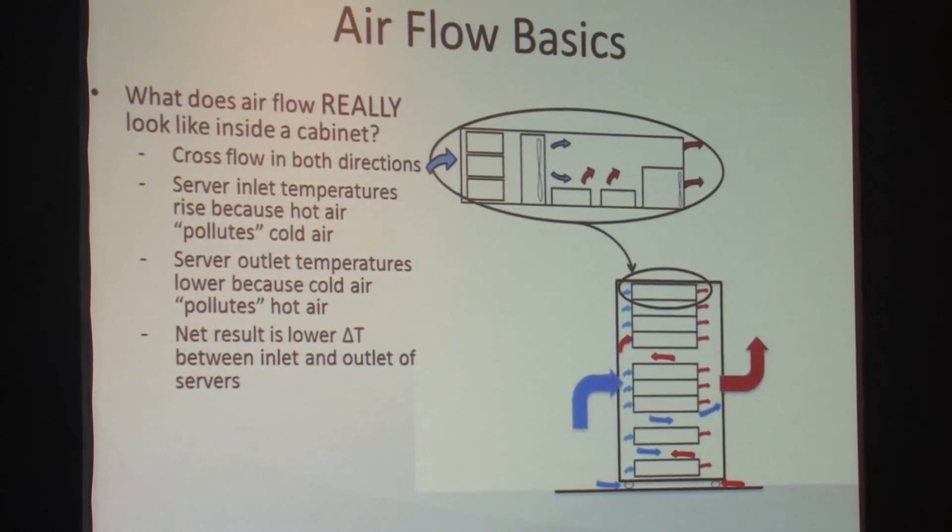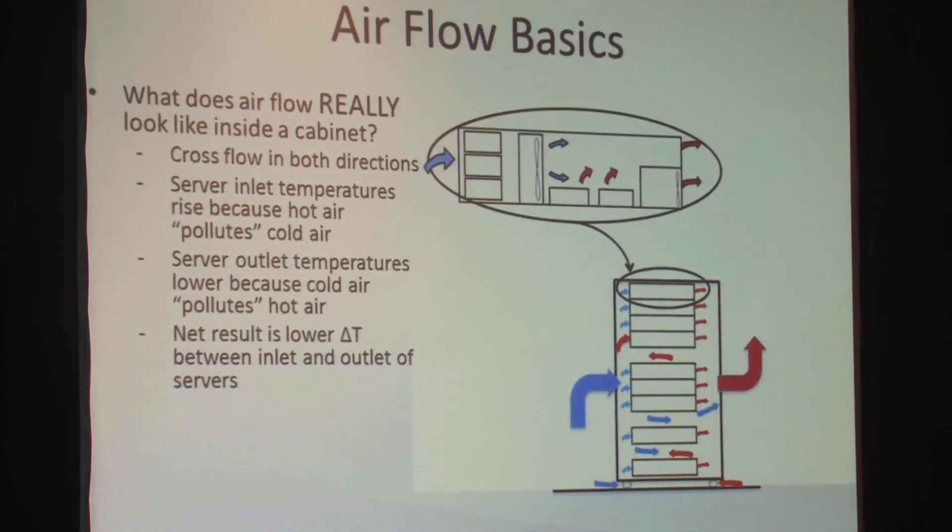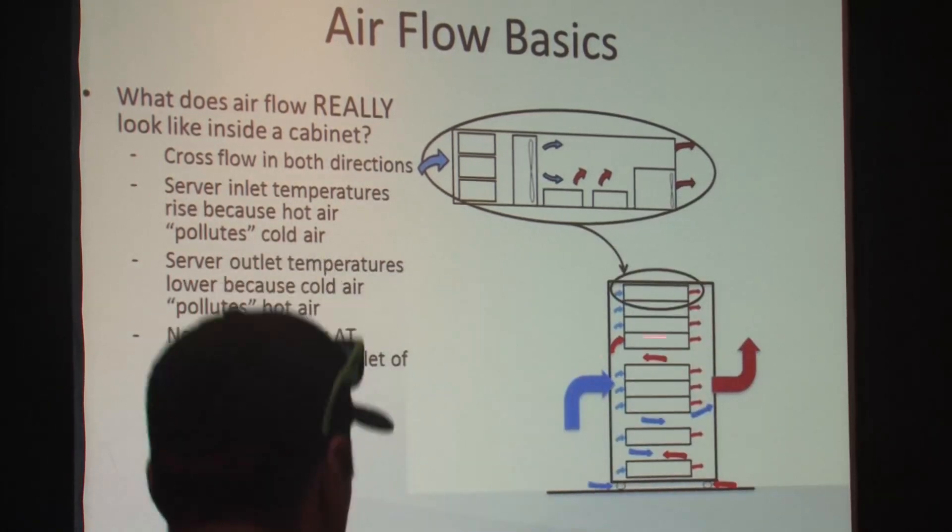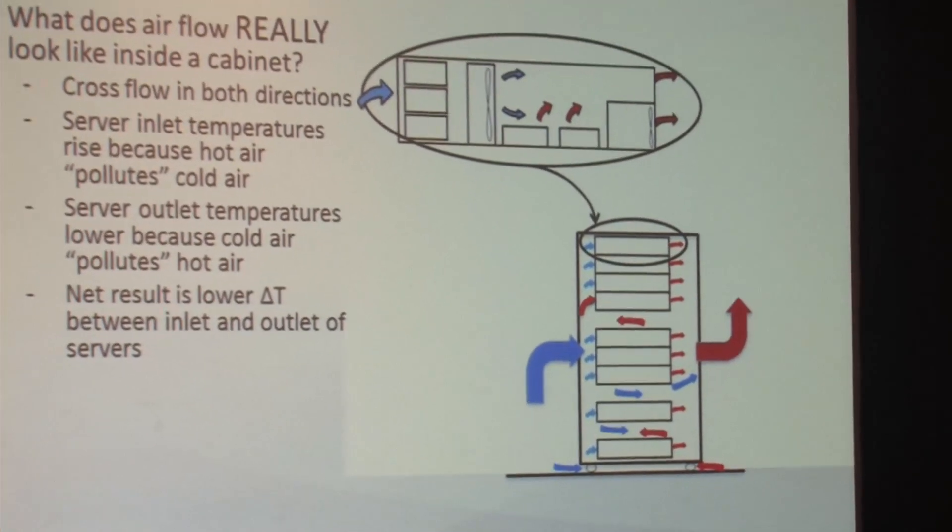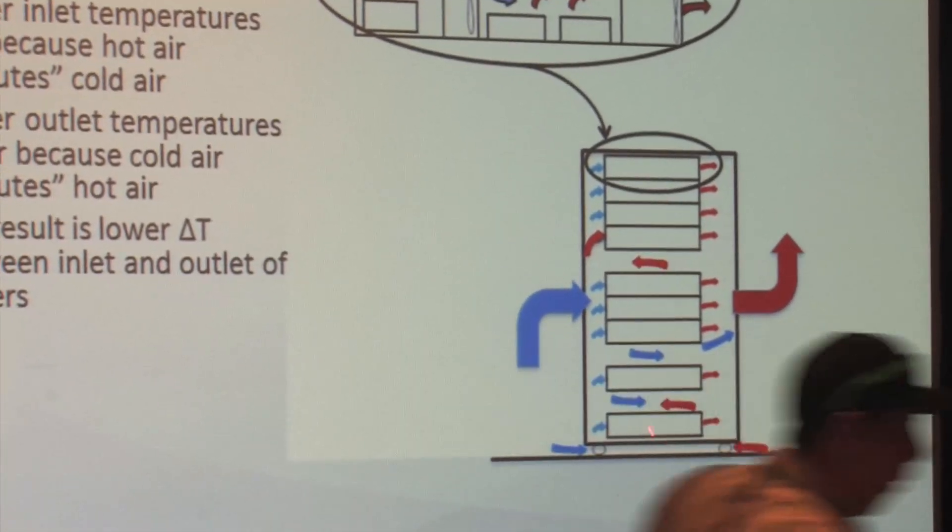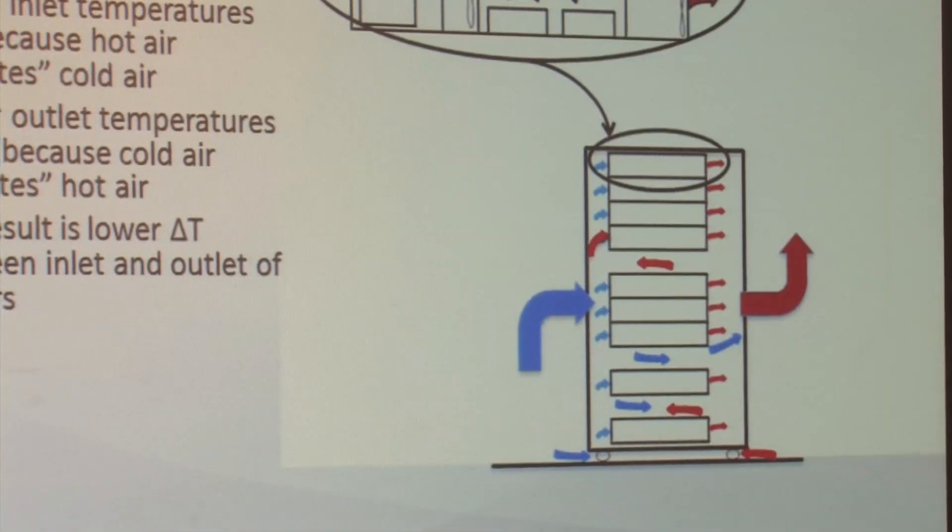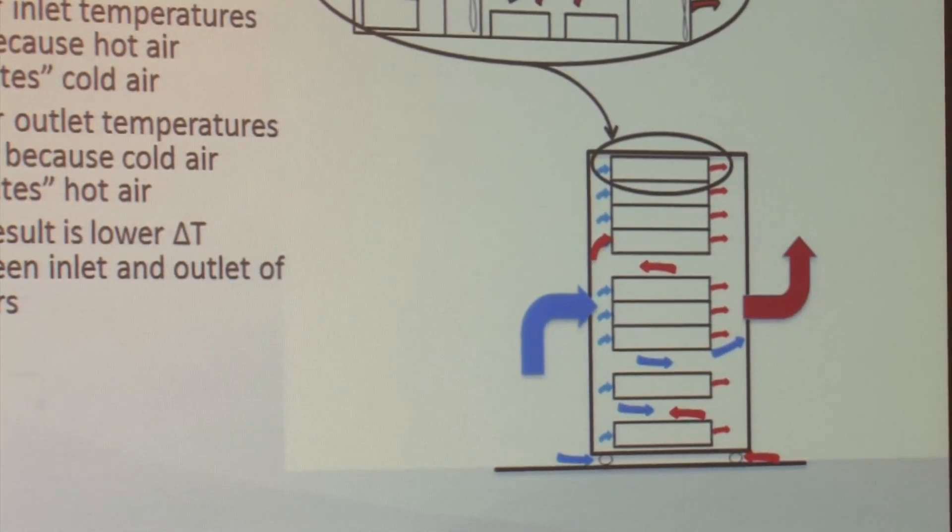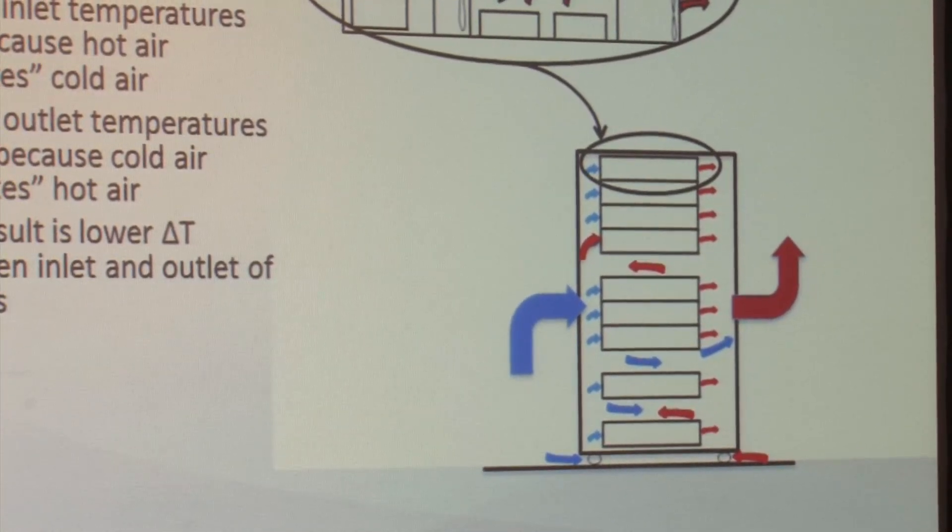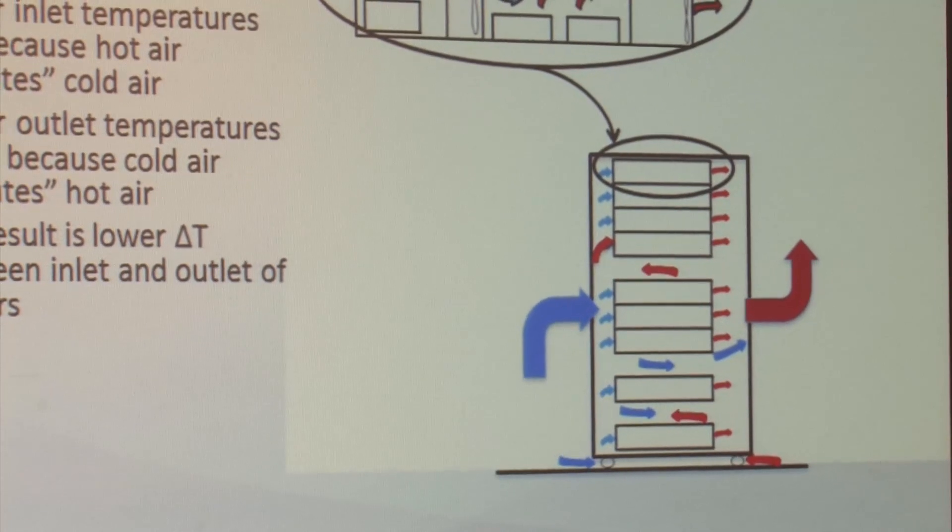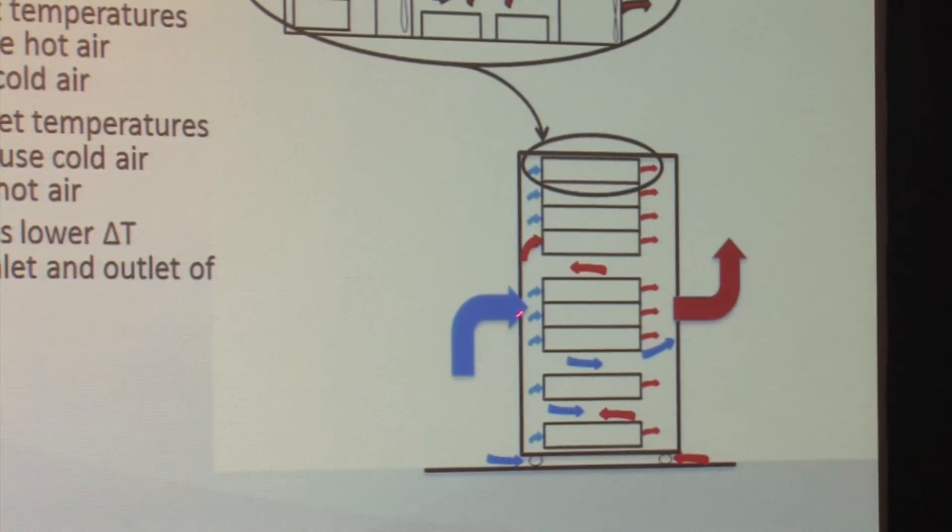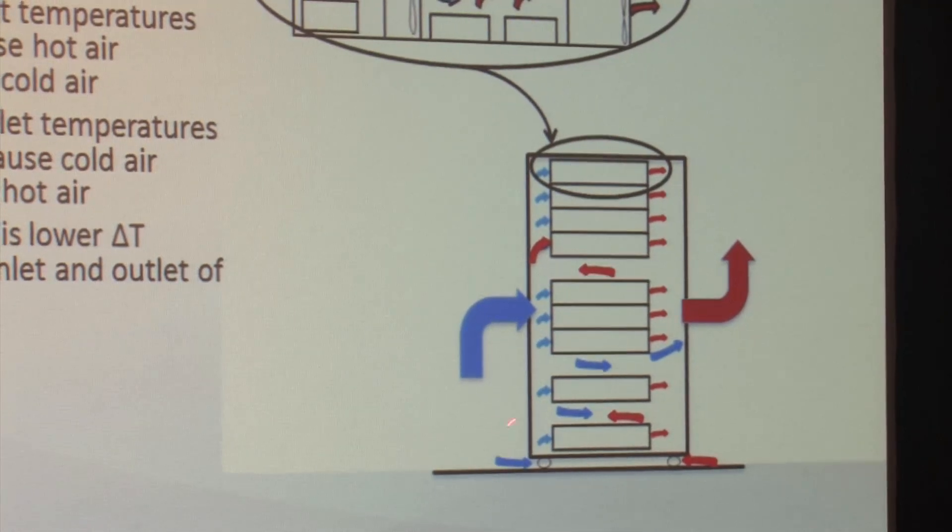So inside this box, you've got a lot of inefficiencies. How many people have not seen these little pass-throughs here? Okay. Or how about gaps between the cabinet and the floor? Maybe there's a set of wheels. I doubt that most data centers actually have any kind of blanking panel right there. So in the real world, you've got your temperature in. And for the most part, most of the air goes through like a perforated plate.